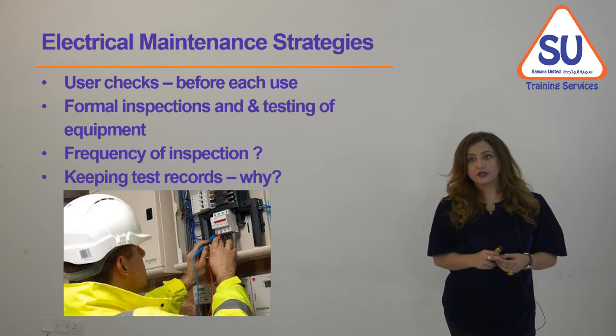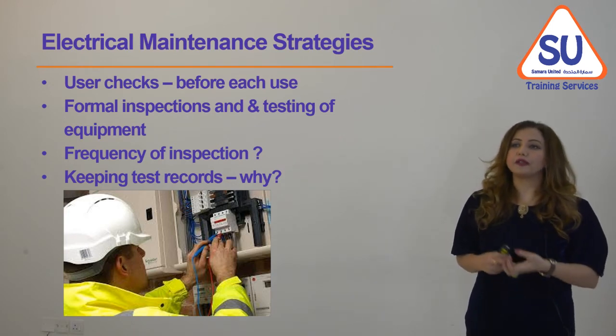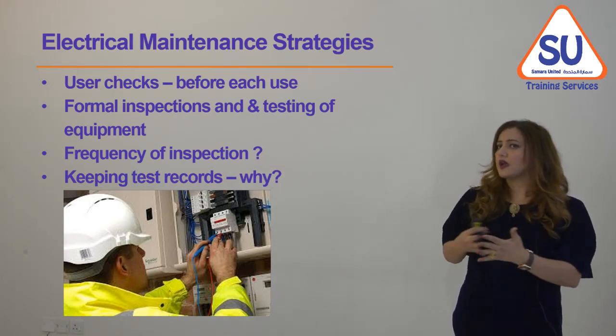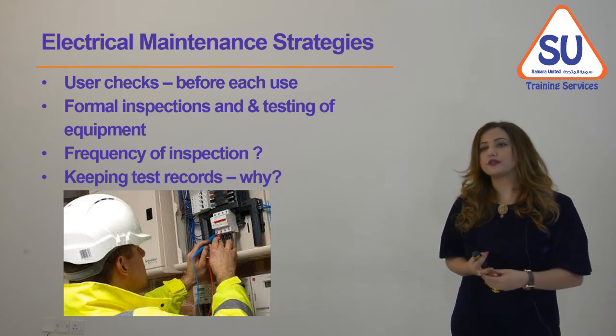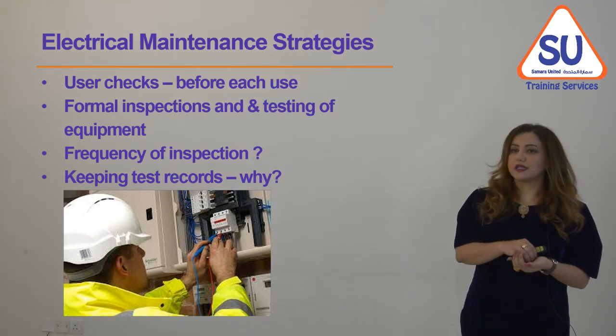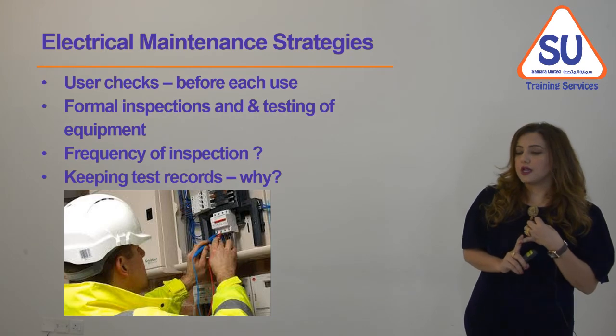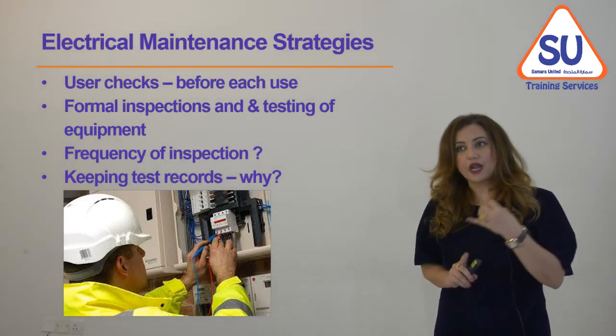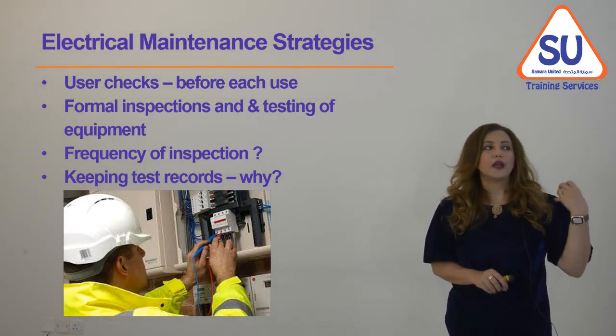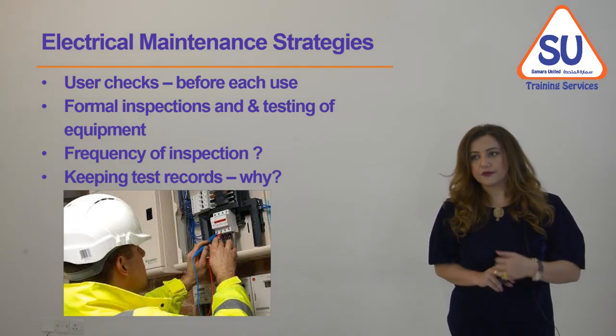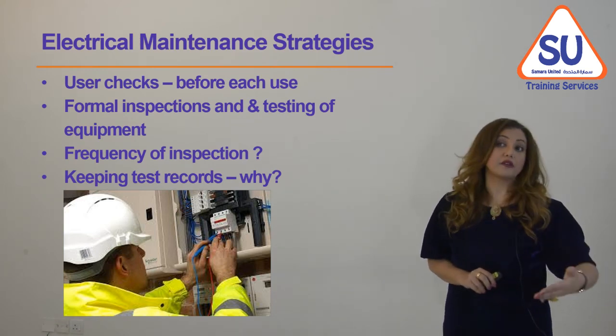Regarding electrical maintenance strategies, we need the user to check the equipment before each use and preferably after use as well. Formal inspection and testing must also be conducted by a competent person. How frequently formal inspections should occur can only be determined by reading the manufacturer's manual and guidance, taking into account the atmosphere in which the equipment is used, the frequency of use, and the load placed on the equipment — these factors may shorten the inspection interval from six months to three months or less.